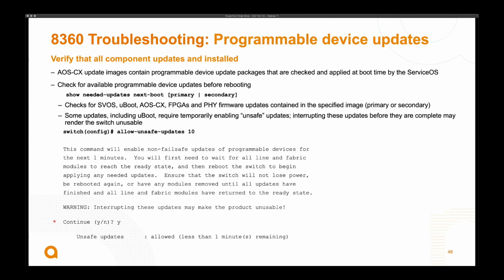Moving to the system maintenance side: programmable device updates. Anytime you update the switch to a new software version, that .swi image may contain updates for different components that make up the overall switch system. This includes the bootloader, service OS, the PHYs, the PLDs — basically all the different components inside the switch that have their own individual firmware. Those can all be updated by the system, and when updates are made available, they're contained within the switch software image and run when the switch is rebooted into that new image.